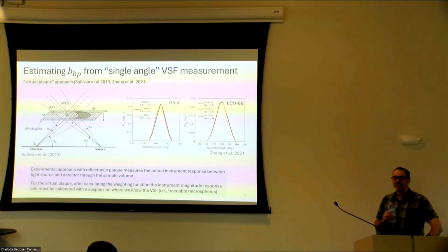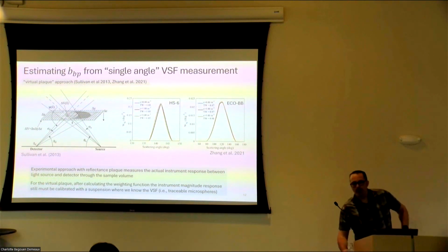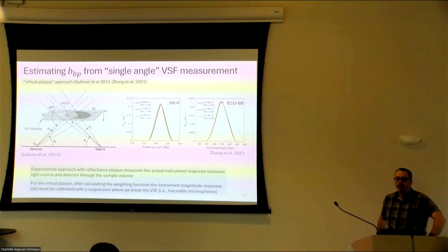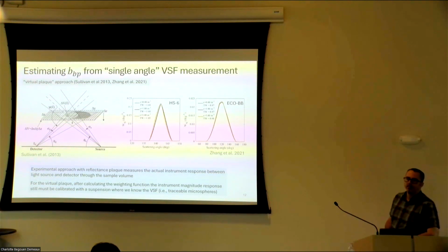Yes. So this angle is based on the construction of the instrument that's not actually validated. You also assume that your source is a homogeneous emission. And if you ever look at an LED, you see that it's not necessarily so, but the assumption is made in the calculation. So these are things that you assume are correct without checking.